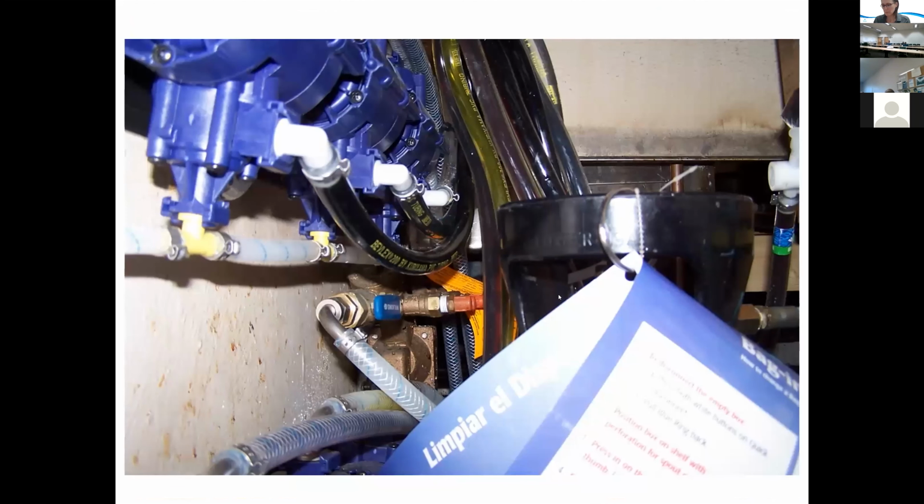This is always a fun one. Can you even find the backflow assembly in here? When you're building a building with fountain soda machines on the table, the building officials will come in and make sure that the RPBA is installed, but that's usually before the soda equipment comes in. They'll sign off saying that the backflow assembly is there, and then the company will bring in all the soda equipment and just bury the backflow assembly underneath all of this stuff because they don't really know what it is.